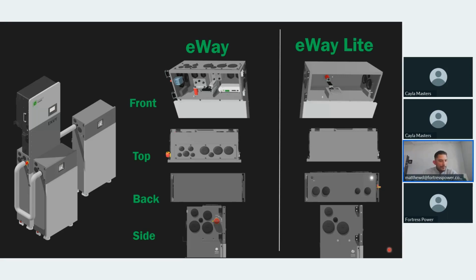My apologies for that. On the side, you have the disconnect, which is the rapid shutdown, which is not really necessary for the eWay Lite, particularly because when you're paralleling, you only need one disconnect to shut down the entire system. And both of them have the power on and off push button on the side. All in all, that rounds up to being more cost effective when purchasing the eWay Lite for parallel solutions or for solutions that really don't need any of these features.